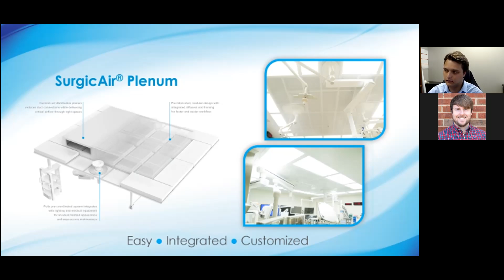During our design process, we provide recommendations on what is really the most cost-effective and best way to go about things. A lot of engineers get excited about plenums quickly because they see the initial benefit of not having to fish individual duct connections in. However, very often we might come back and say, hold on, you could do better, be more cost-effective, and actually avoid conflicts better with a system that has just side inlets or special customized sizes, because every room is different and designed for that specific space. So this could actually be much more cost-effective than a plenum. Basically, we're preventing designers from jumping to conclusions that might not actually be in their best interest at the end of the day.